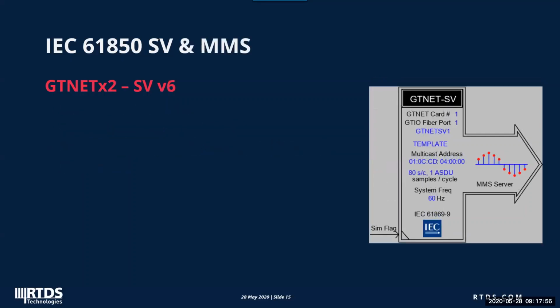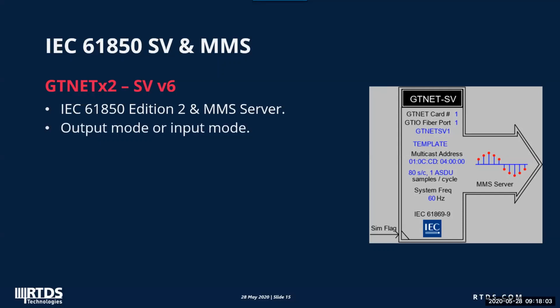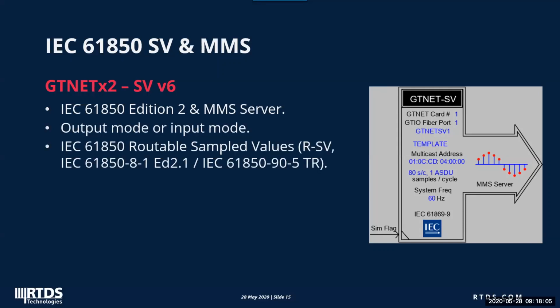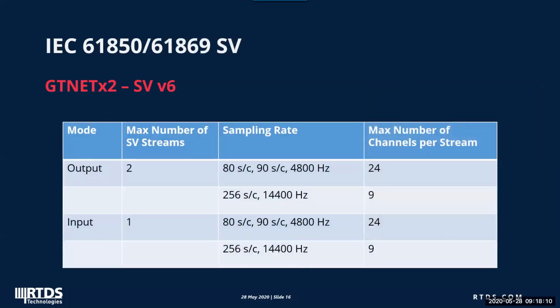Like the GSE version 6, SV V6 component supports edition 2, server and routable sample values. Compared to SV V5 component, more sample rates are supported in version 6, as shown in this table. Depending on the selected sample rates, up to 24 data channels may be included in the published or subscribed SV stream.